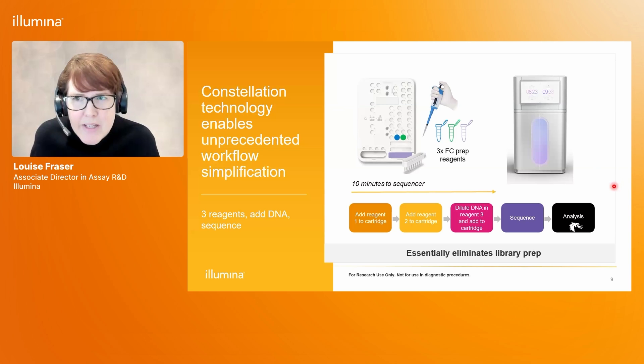We can achieve all of these benefits to genome completeness with a very simple workflow. Shown here is what the user needs to do to complete the Constellation sequencing run, starting from a purified DNA sample. Users are supplied with three frozen reagents indicated by three colored tubes. Two of those reagents get added directly to the sequencing cartridge, and the third reagent is used as a dilution buffer for the DNA samples, which are then added to the library strip tube. This all gets loaded to the sequencer in about 10 minutes of hands-on time. Once loaded, the rest of the workflow is completed by the sequencer and analysis is completed through DRAGEN, essentially eliminating all upfront library prep.